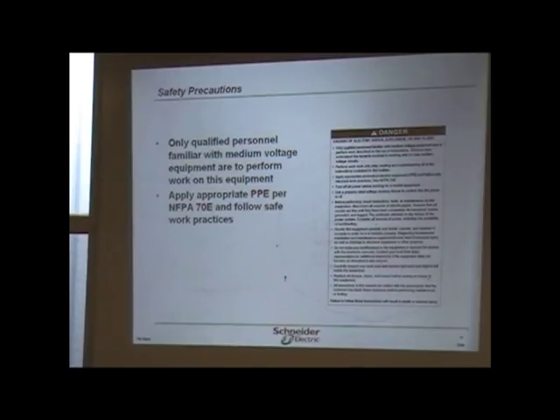Your gloves should be tested every 6 months. If you have a hot stick, it should be tested like every 2 years. If you have a mat, I think it's about every 2 years as well. All that stuff needs to be sent out to a laboratory that does dielectric testing, almost like you saw, where they put like 23,000 volts across it, one clip on one side, one clip on the other, to make sure it doesn't track or conduct, to make sure it actually insulates you from any potential hazard.